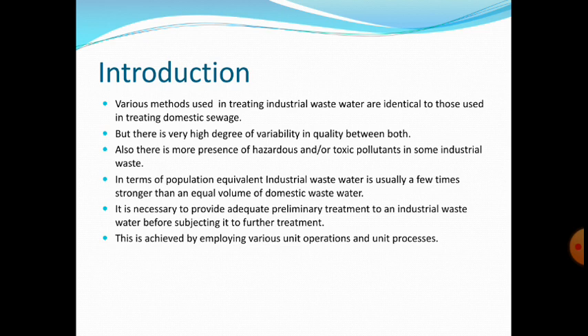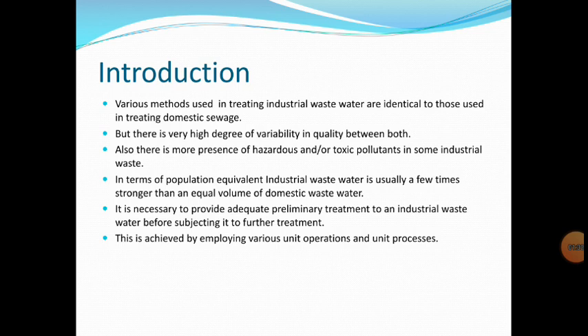Second, there are large variations in the flow rates of industrial wastes. And third, the presence of hazardous or toxic pollutants in some industrial waste. In terms of population equivalent, industrial wastewater is usually a few times stronger than an equal volume of domestic sewage, meaning industrial waste has a higher concentration of pollutants. Given the possible presence of hazardous or toxic pollutants, adequate preliminary treatment must be provided before further treatment.